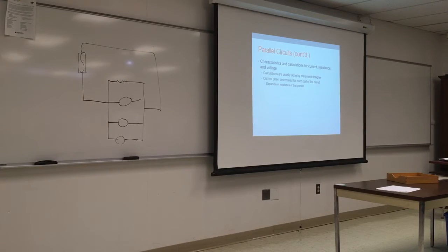And if you're not, how do you check if that current is being drawn or not? Use the clip-on meter. So if I did the calculation, it's supposed to be half an amp, and you flip on the ammeter, and it gives you 0.3 amps, something's wrong with the equipment. If it gives you 8 amps or 0.8 amps, you know something's wrong. You're supposed to have the right amperage. If you have more amps, it means something is drawing more, and that's not good for the circuit.